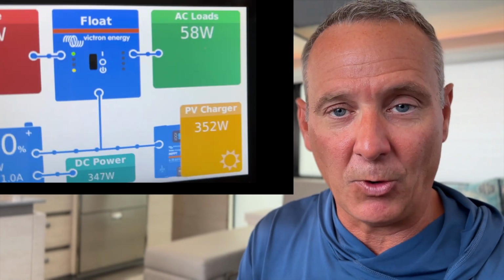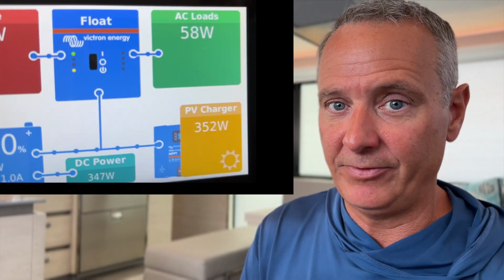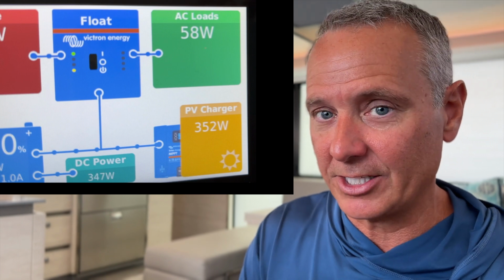Before I swapped out any pumps, I wanted to get a baseline reading of the stock system as it comes from the factory, isolating just the power draw of the water pumps in the chiller system. So I shut off everything on the 240 side, and it stabilized right around 50 or 60 watts. I believe that's just what the Victron Quattro takes to run itself. The 110, I'm told, all the 110 volt systems, since it's inverted, those loads do not show up on the AC loads side of the Victron display, so that is only 240.